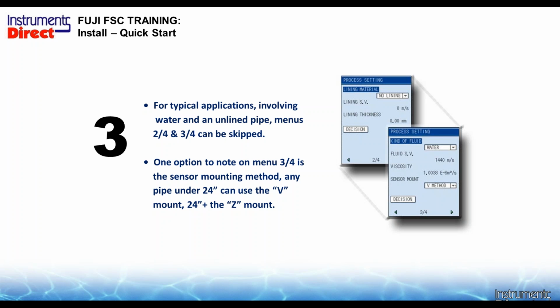If you had a water and glycol mix, the traditional 30% glycol, 70% water, if you do the math on the sound speed, you'll find out that it's still within the plus or minus 10% of the sound speed. So with 30% glycol and water, you can actually use water. If you had 72.5% glycol, then you may have to calculate it out and put the sound speed under other there. But for most cases, almost everybody's application being water, maybe an oil, those are where you're going to stay from the drop-down menu.